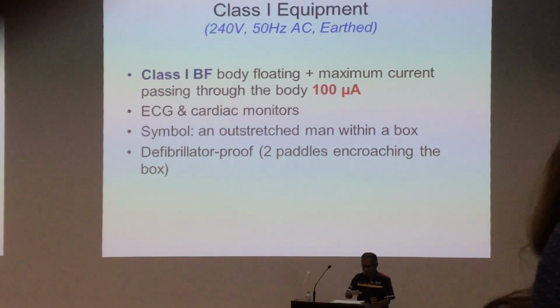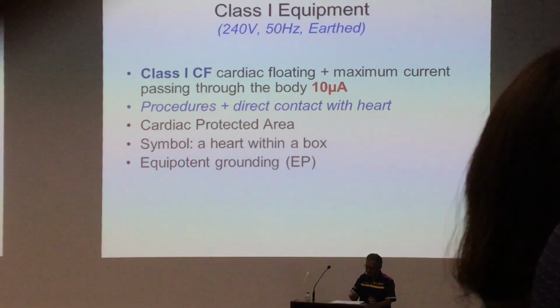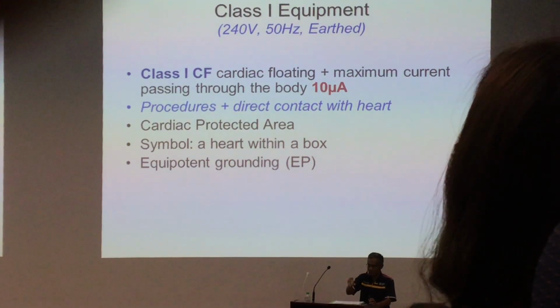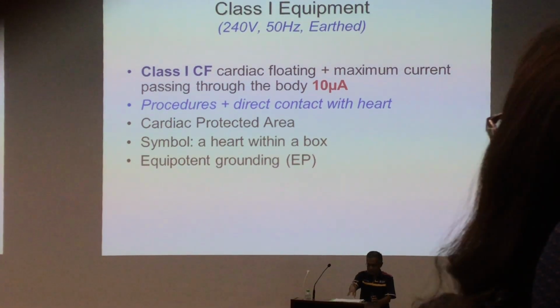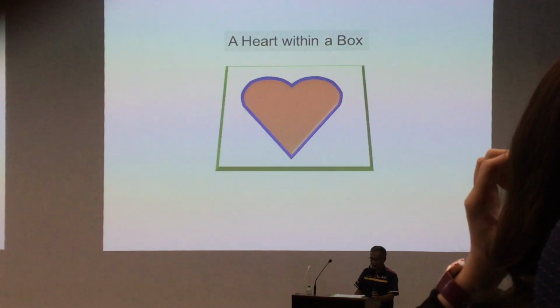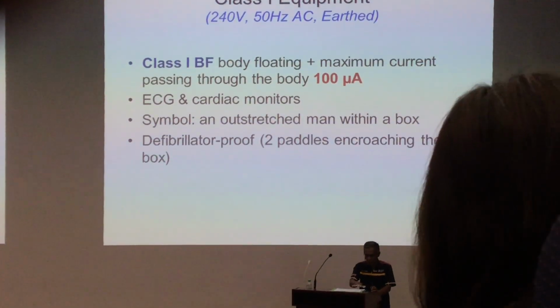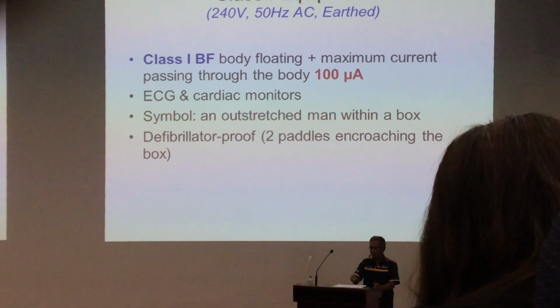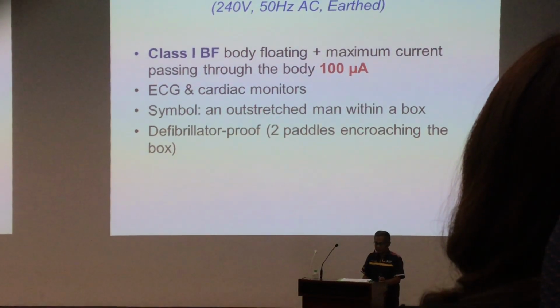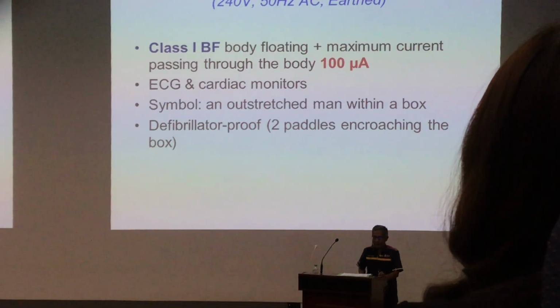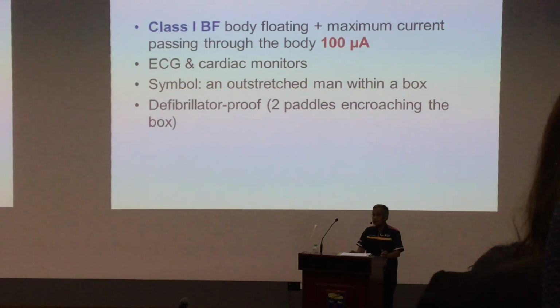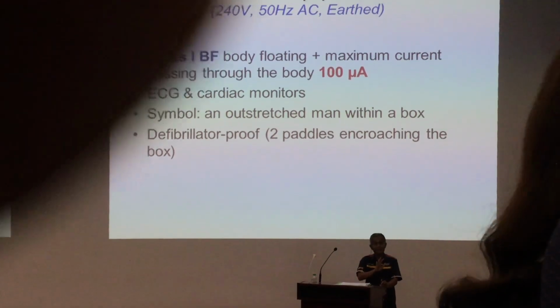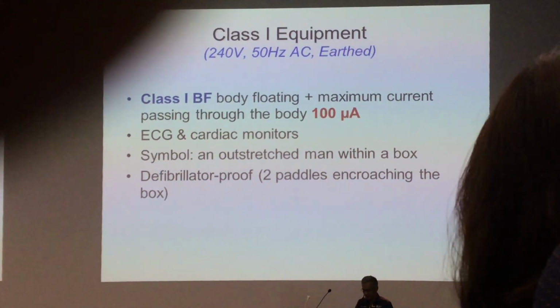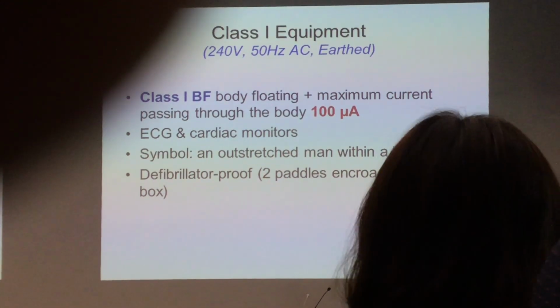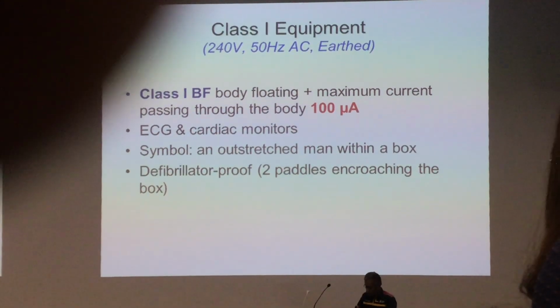Class 1 is further divided into two. This is the ideal: cardiac cath lab, CABG, pacemaker. This is the place, 1 CF. The other one, 1 BF, is slightly higher than 1 CF, because the setting of this electrical classification is different. The 1 CF is more costly. That's the only difference, right? And it is safer for cardiac procedures. This is less safe. You can, but it is less safe. You can still do it. But don't do cardiac procedures in class 1 BF.